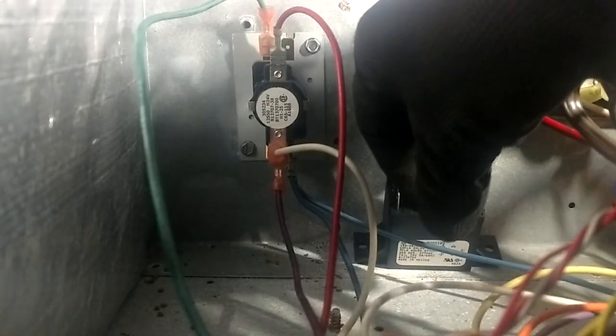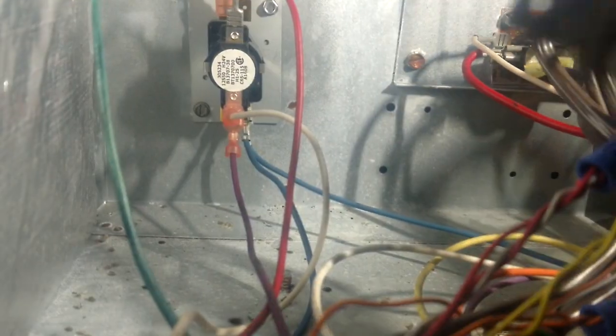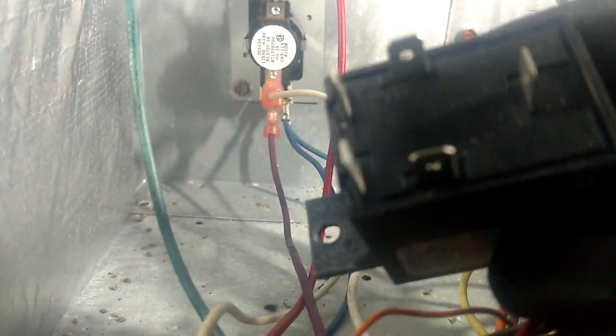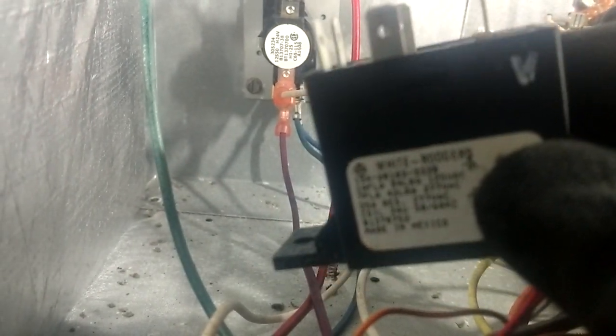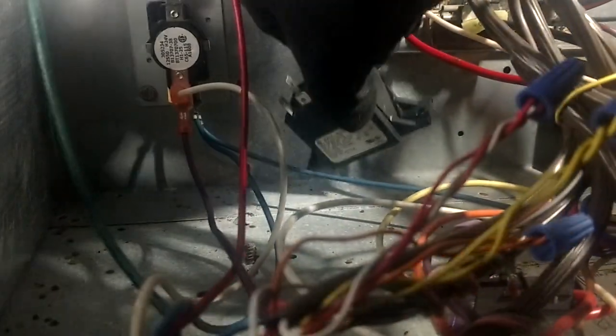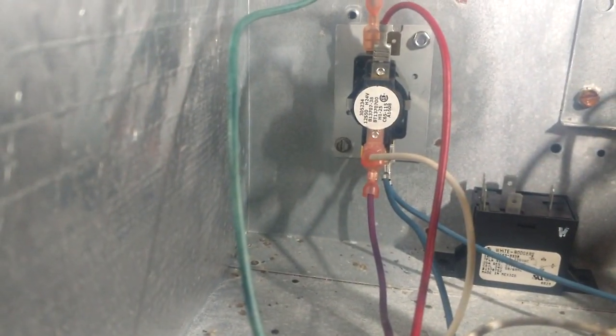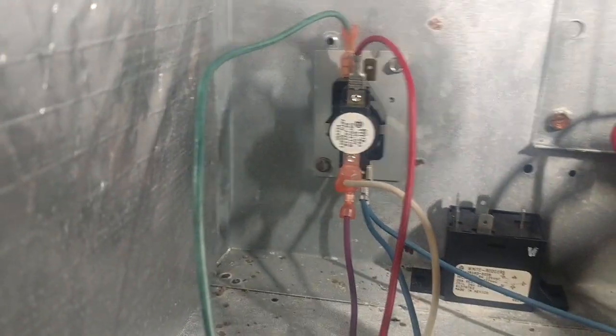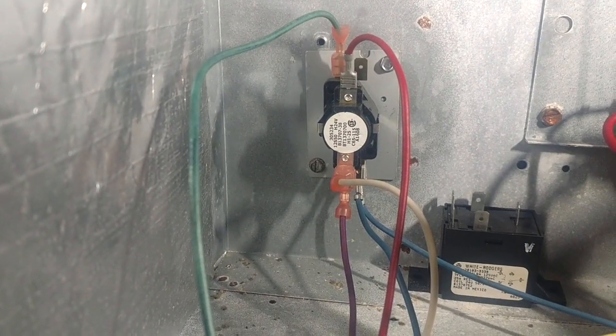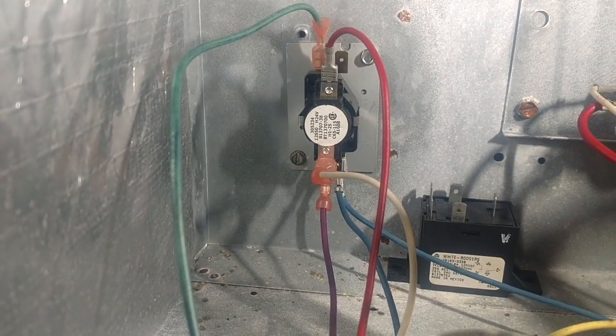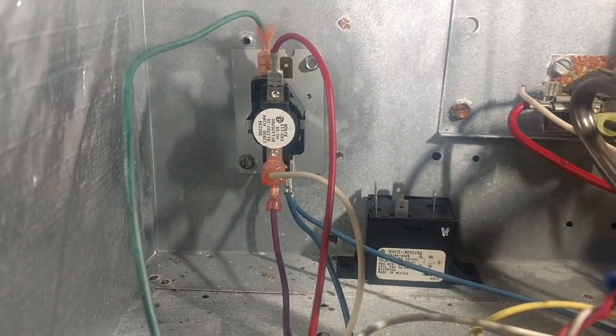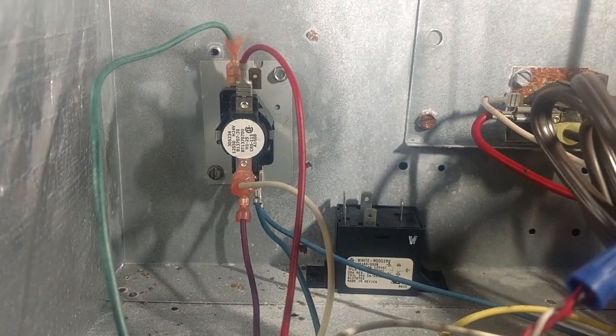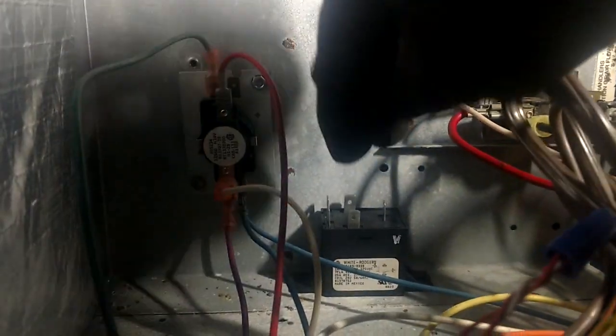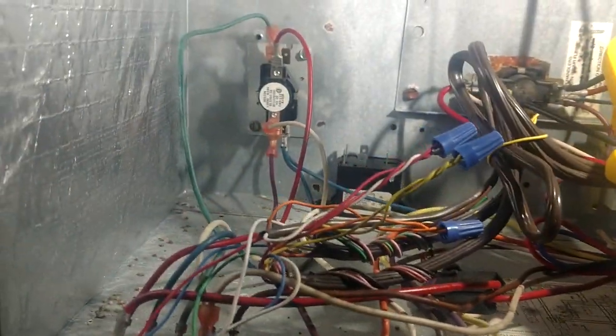Some people, like Lennox, don't even use a relay to do that. And you can see that the original manufacturer's relay was replaced some years ago, and they switched it to that style of relay. That's what Ferguson sent as a replacement for this thing. And they have since changed to another relay. I just did one on an Amana unit the other day that had this type of relay, and they were actually switching to an ice cube relay.